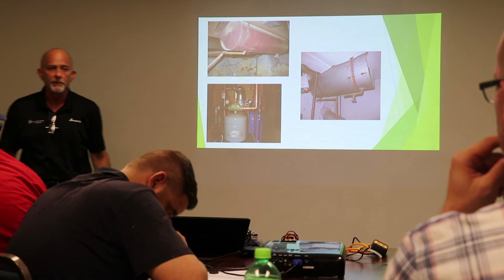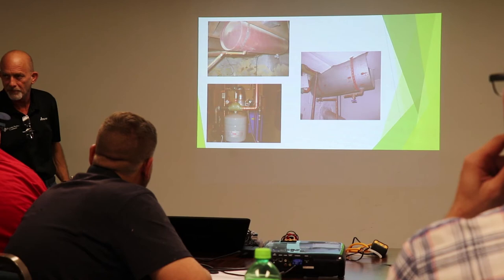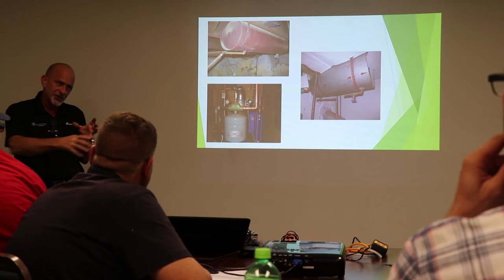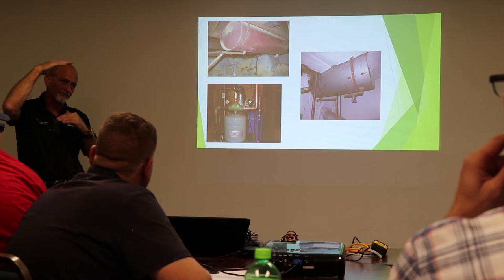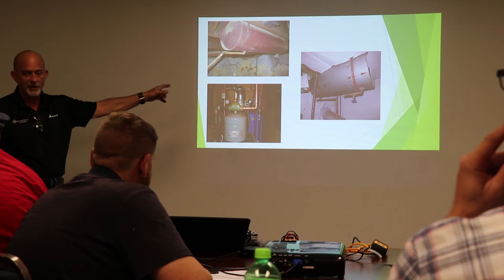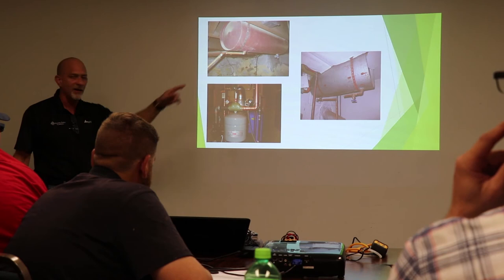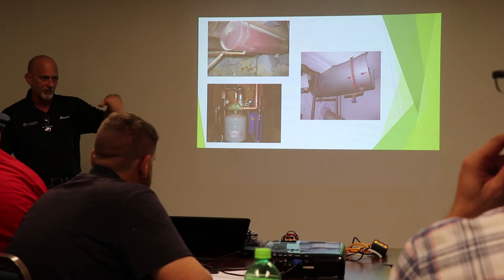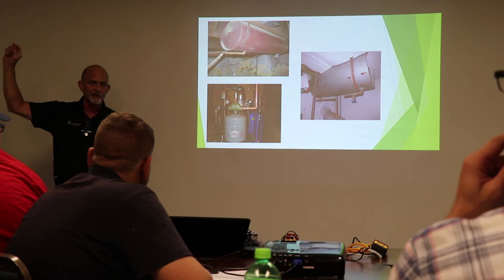Old timers on some of the old tanks, like that gray one, didn't really have a bladder in it, but the way it was made, you'd have to crack a union open, and it would suck air up in there, and then the water would just have like an air cushion inside that tank. You normally would know that because on the drain valve they had a garden hose hooked to it. So when it got too full or their pressure relief kept opening up, they'd drain their tank, shut it off. Usually a secondary valve that they can open up, it would suck the air in, and they'd be ready to go.